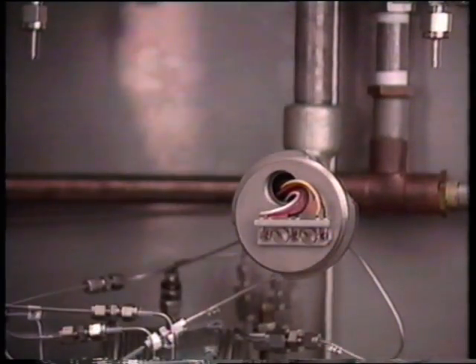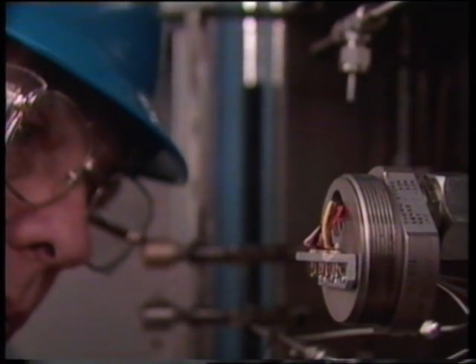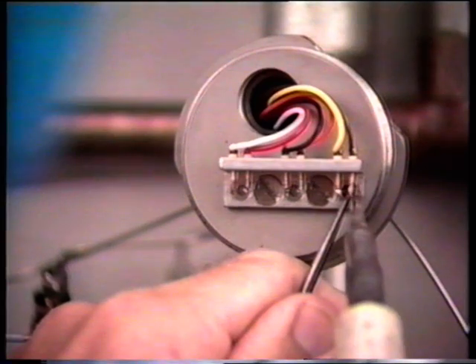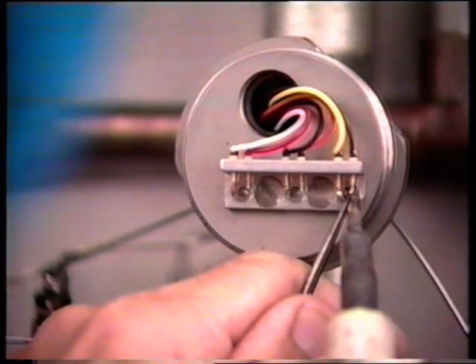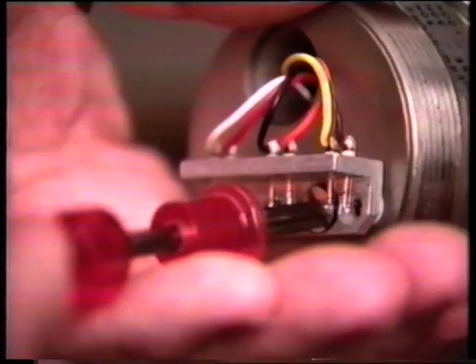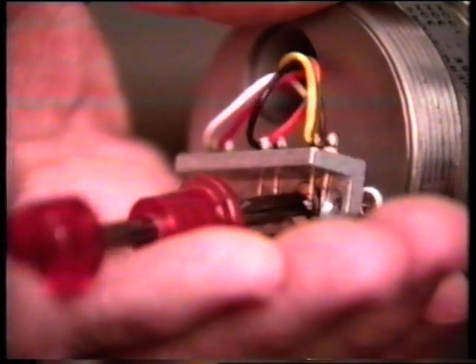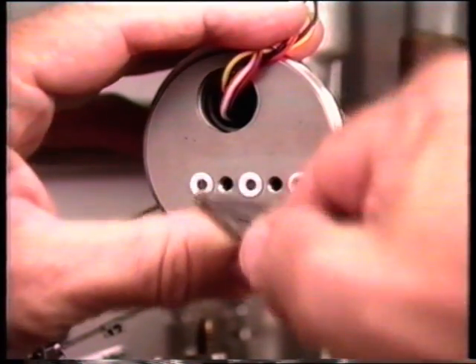Remove the detector cover and inspect the thermistor wires for damage or stress. The sense and reference thermistors must be replaced as a set. This is the intercolumn detector, which is discussed in the student workbook. To replace the thermistors, unsolder all leads from their feed-throughs. Remove the two screws and lift the retainer plate away from the detector body. Leave the wires attached. Lift out the thermistors.